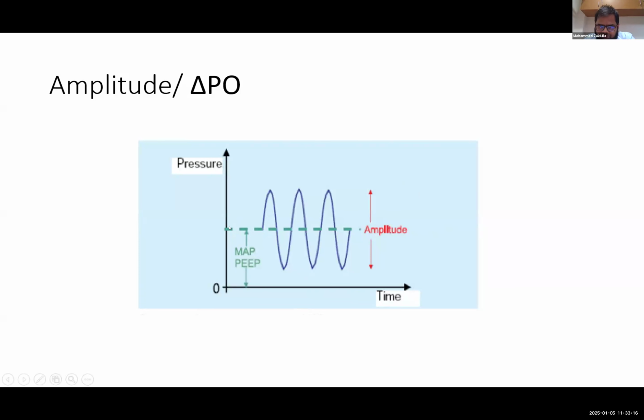So you will give that continuous pressure, and on top of that, you will give the amplitude. Once you start a pressure of 10 or 12, you usually start with an amplitude around 20 to 30 in most babies, roughly double the MAP which you start with. So an amplitude of 20 means there will be a forward push of 10 and then a backward push of 10.